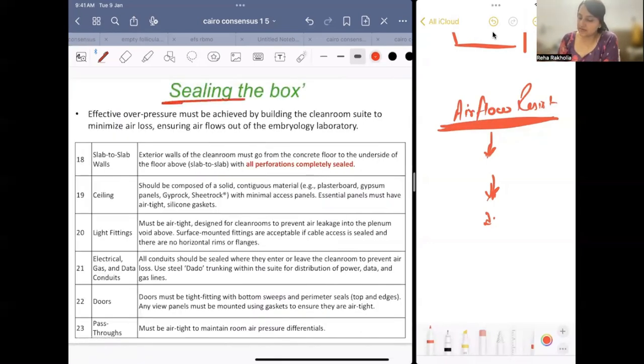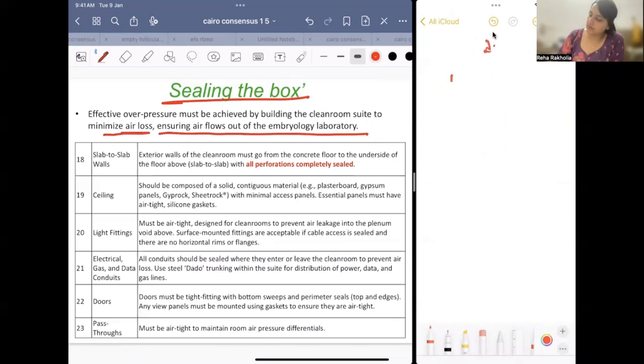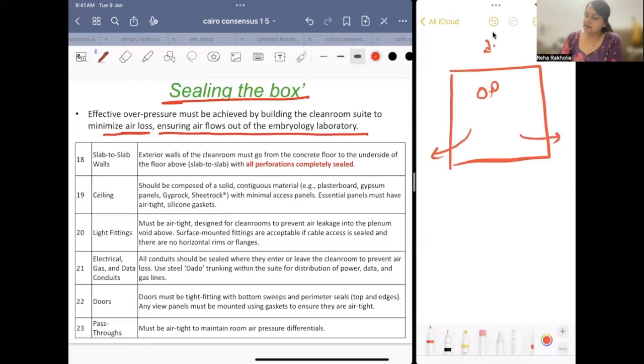Sealing the box. Effective overpressure must be achieved by building a clean room suite to minimize air loss, ensuring airflow out of the embryology laboratory. See, we have to maintain the overpressure so that the air flows outside of the laboratory, and so that dust and other particles do not enter the lab, the IVF lab.